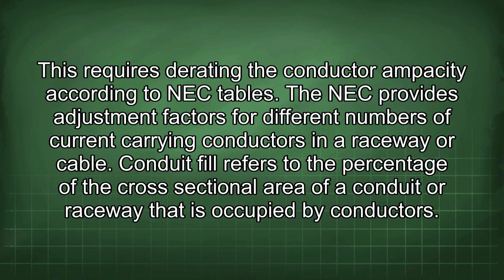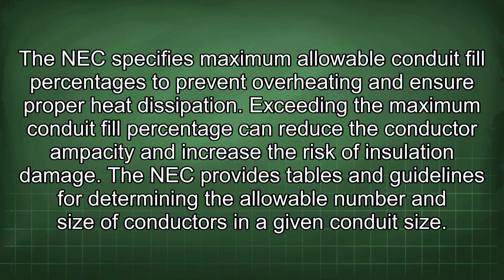Conduit fill refers to the percentage of the cross-sectional area of a conduit or raceway that is occupied by conductors. The NEC specifies maximum allowable conduit fill percentages to prevent overheating and ensure proper heat dissipation. Exceeding the maximum conduit fill percentage can reduce the conductor ampacity and increase the risk of insulation damage. The NEC provides tables and guidelines for determining the allowable number and size of conductors in a given conduit size.